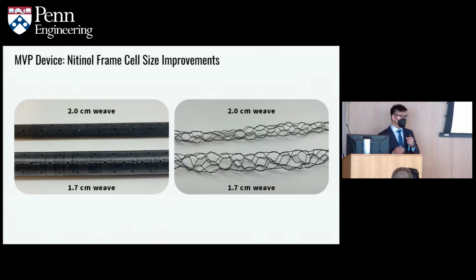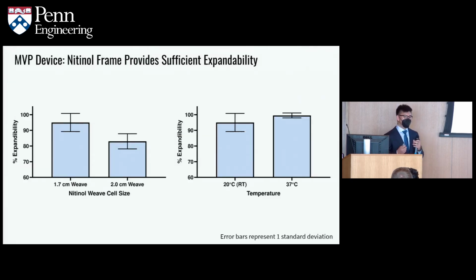For the MVP, we used 2 iterations of the frames with varying mesh or cell sizes of 1.7 and 2 centimeters to assess the effect of varying cell sizes on the expandability of the device. On the left, we could see the guides that were used to create the frames, and on the right, we could see the resulting frames. To measure expandability, we would compress the frames and allow them to expand at room temperature. And we found that a smaller cell size of 1.7 centimeters allowed for greater expandability, or ability to revert back to its original size, compared to a larger cell size of 2 centimeters. Focusing on this smaller cell size, we then assessed the effect of varying temperatures. And we found that more physiological conditions at 37 degrees Celsius resulted in a greater expandability compared to room temperature conditions.